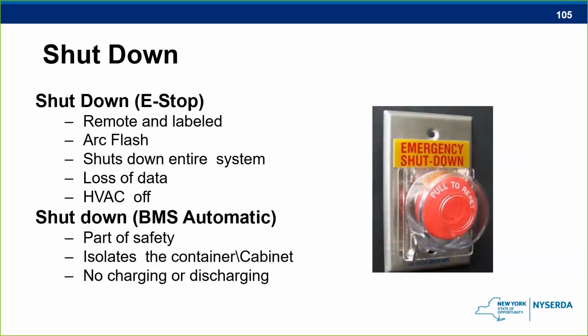Also, does it shut down the HVAC system? If it's in the middle of the summer and the sun is beating down on these things, could we have a problem if the HVAC goes off? These things are what they call the Goldilocks batteries, the lithium ion. They need to be just right, just the right temperature for optimum efficiency. So when we shut down the HVAC, are we actually causing a problem? Something to consider again.